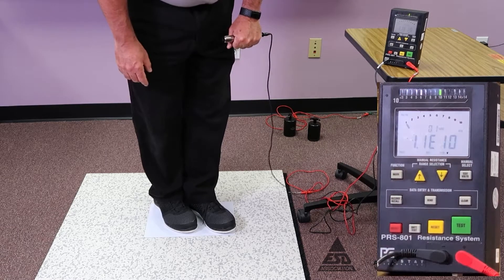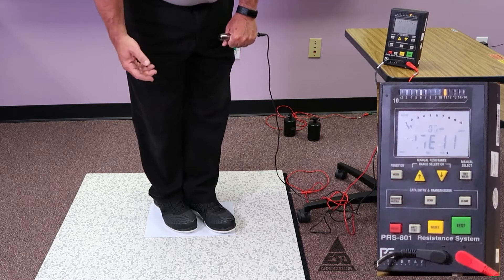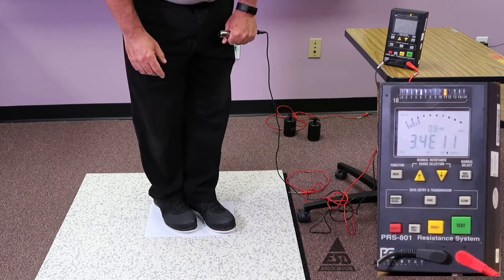If we look at the first measurement, you can see with the insulator there, I'm at 10 to the 11th ohms, well above the 10 to the 9th, which is a requirement for the system.